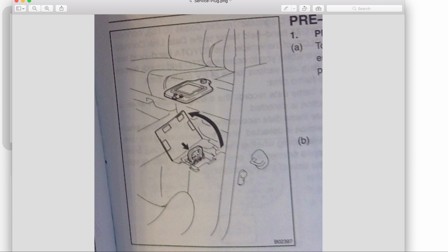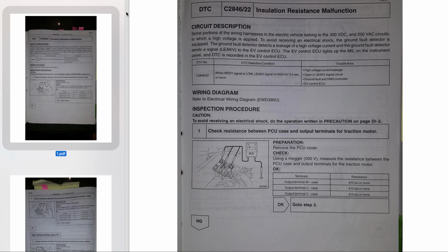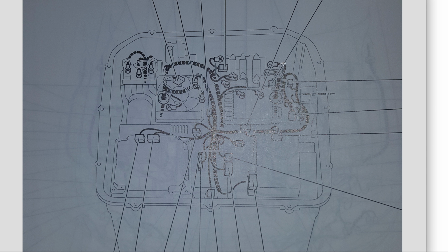And then once I go into the power control unit, I do some voltage checks on various things just to make sure that there is no voltage. On this one, there is no voltage present here to ground, here to here, and here there shouldn't be, but here to ground. All of these different key places, to make sure that there's actually no voltage present before you start connecting a megger. So going on to what the repair manual has you do.